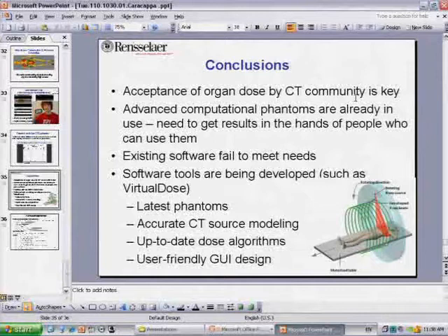Yes. So one last question: the largest phantom that you displayed had, from my estimation, a BMI of about 30. But we know we have patients who have BMIs of 40 and even 50, and I wonder if you're moving in the direction of modeling the severely obese person. We've already done work up to BMIs of, I think, 45. In fact, I think there's a paper later on about certain doses. But yes, we can go up to very severely obese models.